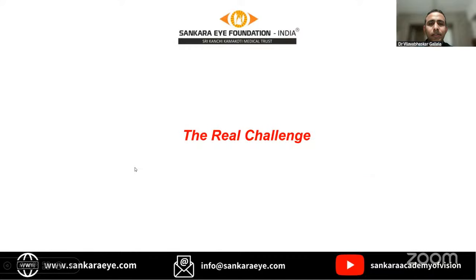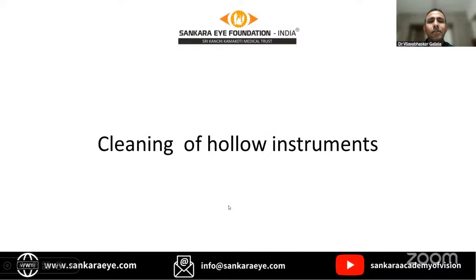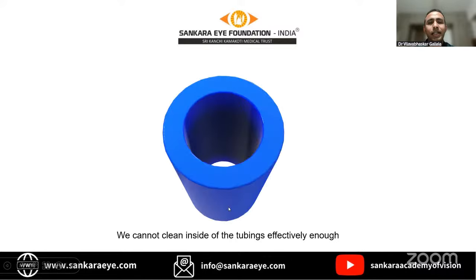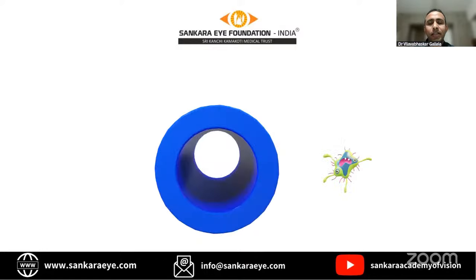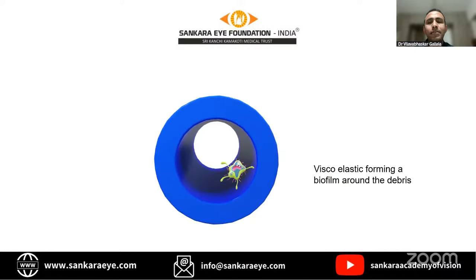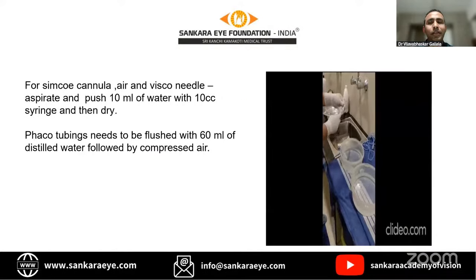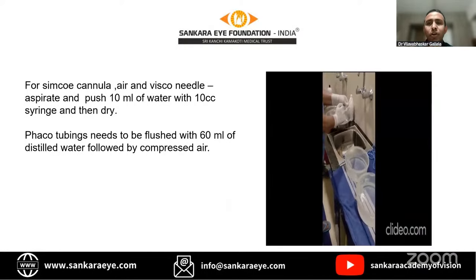After that, the real challenge. As I have mentioned previously, ophthalmology is a galore of hollow instruments. The cleaning of hollow instruments is the real challenge in our specialty. We cannot clean inside the tubings effectively enough. If you don't clean it properly, there may be microorganisms inside this tube, and viscoelastic can create a film-like structure, biofilm, which prevents the microorganisms from exposure to the sterilizing agent. So even after sterilization, these microorganisms remain alive and can cause infection. That's why it is critical to clean these hollow instruments properly. We should have a proper protocol for this cleaning.